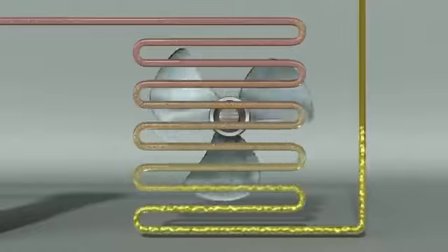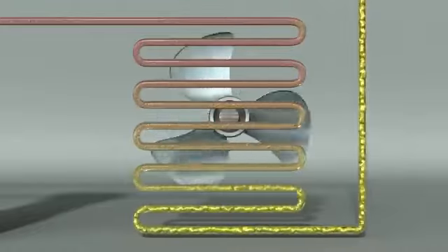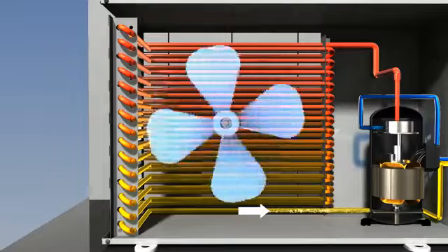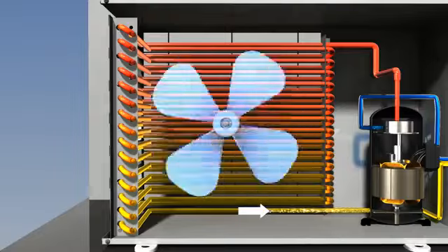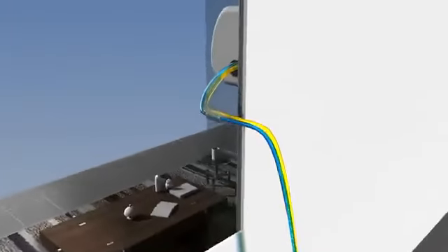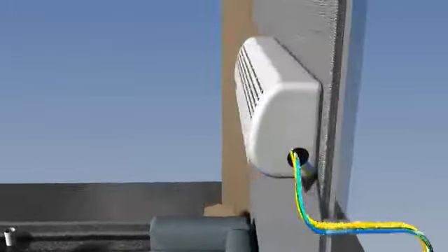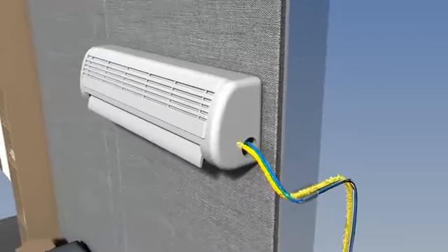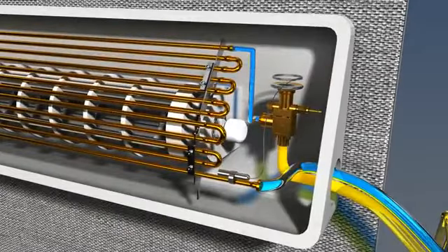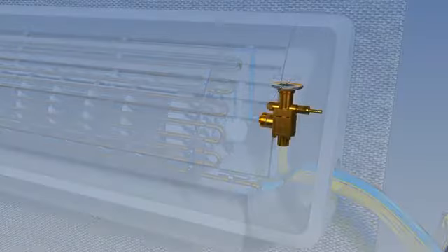A refrigerant in gas state of high temperature loses heat as it passes through a condenser. As such, it becomes condensed and at the exit, it turns into almost liquid. Although the refrigerant has thrown off some of the heat as it passes through a condenser, it is still hot, with temperature at about 50 Celsius. The refrigerant in high temperature and high pressure liquid flows into the expansion valve.